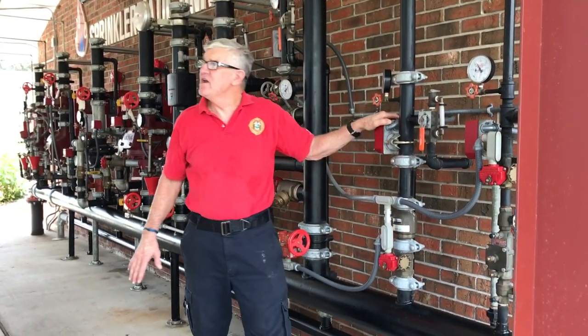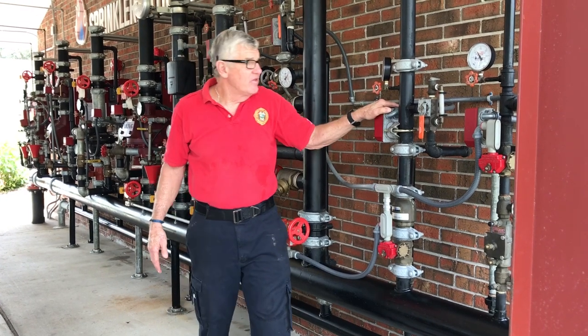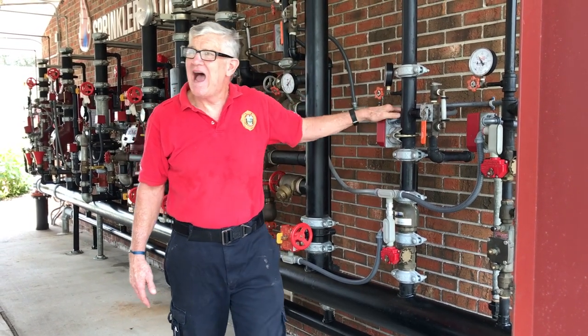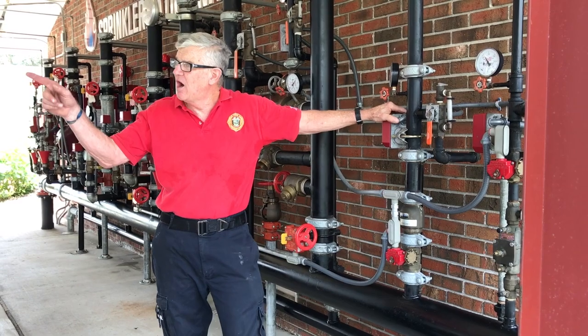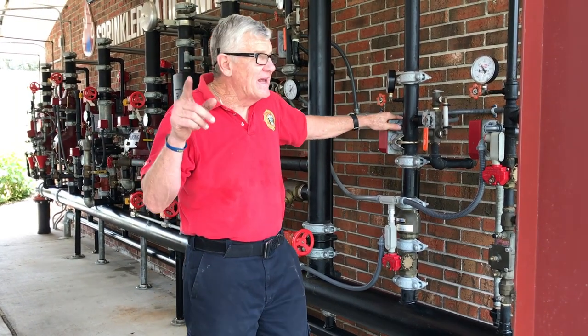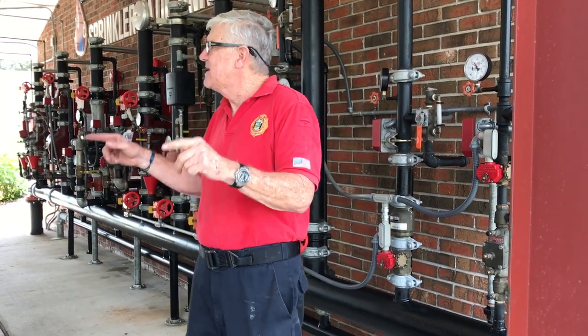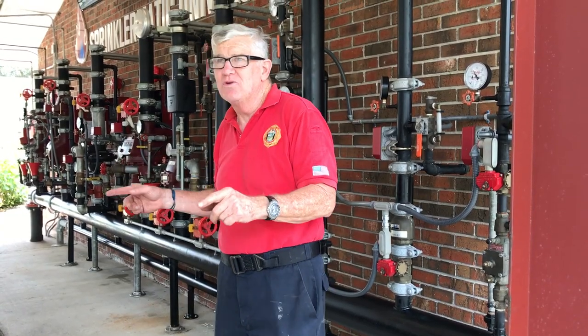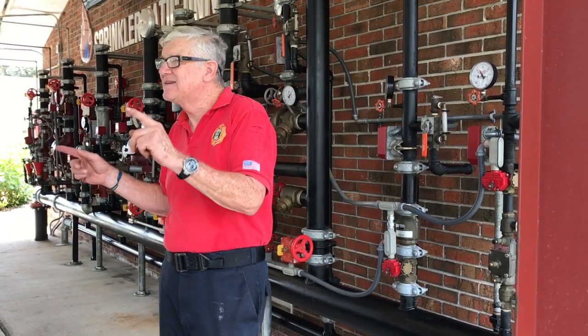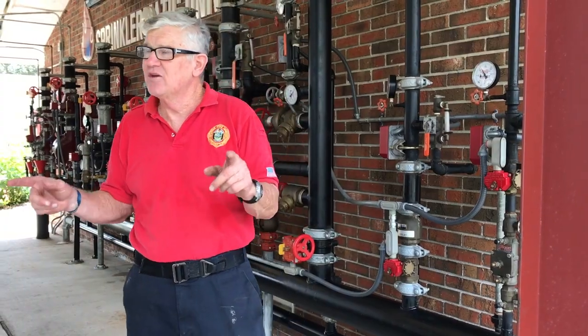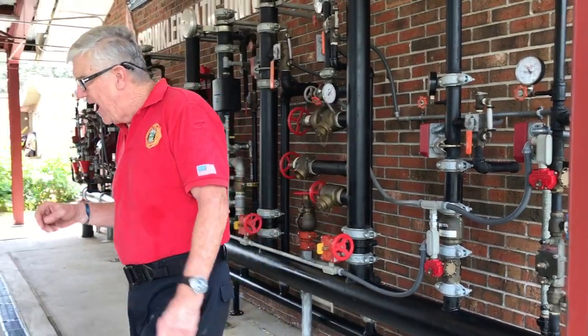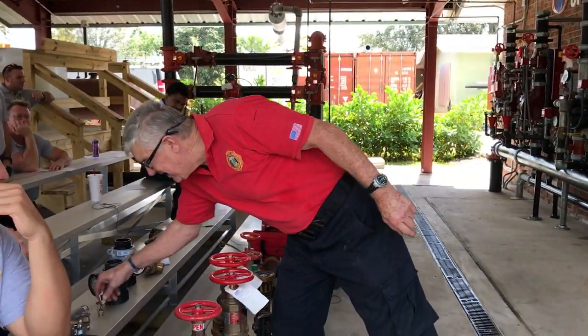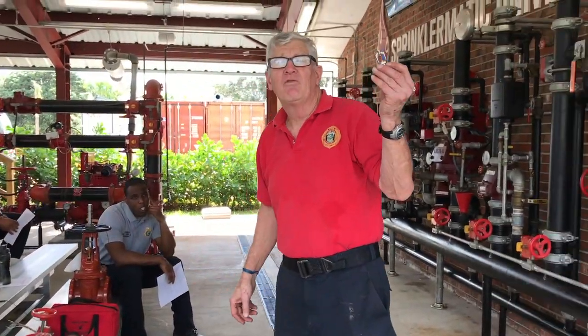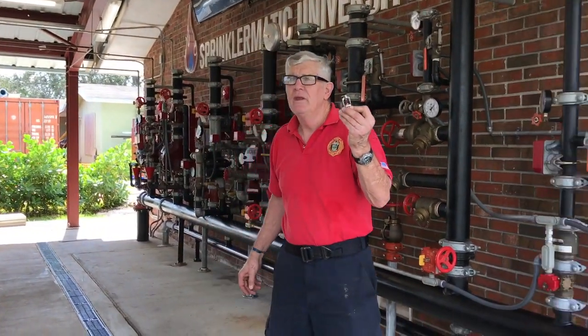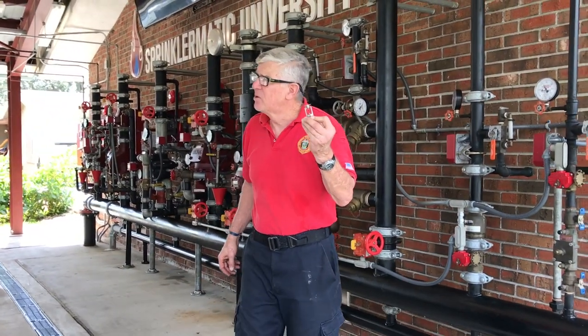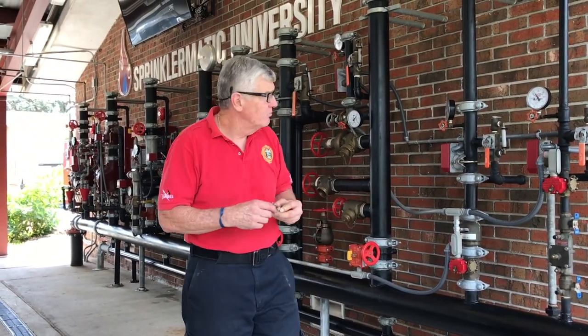Now, these systems are very near and dear to our hearts. This is what's called a 13R sprinkler system, R for residential. It is designed and intended to protect the occupants and buy them time to escape the fire. It is not intended to prevent the building from being destroyed by fire. Why? It flows very little water for a small fuel load. It cannot thwart a determined arsonist.